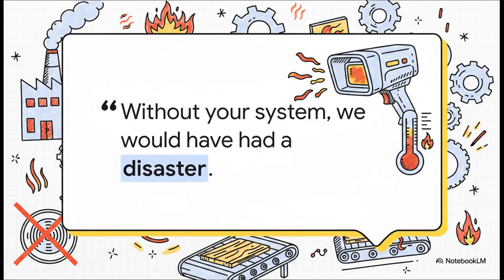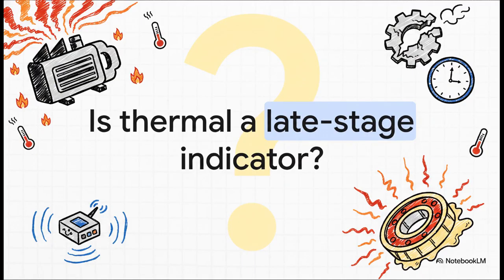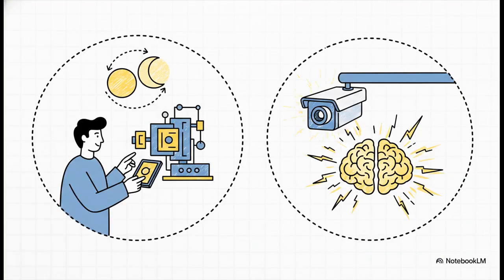down around them. Now, if you've been around the industry for a while, you might actually be wondering this right now. But isn't thermal a late-stage indicator? It's a super common pushback, especially from the vibration monitoring crowd. The thinking goes that heat is just a symptom of a failure that's already happening. So if you're waiting for something to get hot, you're already too late. Actually, if we were talking about a guy walking around the factory floor once a month with a handheld FLIR camera, that pushback would be 100% right. You'd only be catching problems that were basically already on fire.